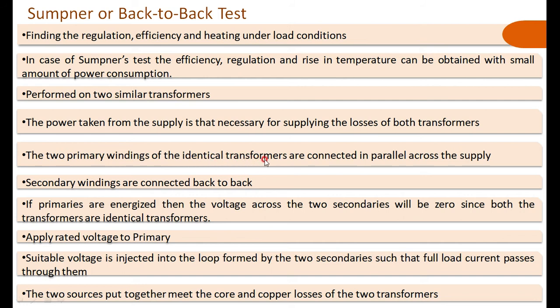The two primary windings of the identical transformers are connected in parallel and connected to the supply. The secondary windings of the two transformers are connected back to back — that is, in phase-opposition. The primary windings are connected in parallel, and the secondary windings are connected in phase-opposition. Rated voltage is applied to the parallel-connected primaries, and rated current is injected into the phase-opposition connected secondary windings — similar in principle to performing an open-circuit and a short-circuit test simultaneously.